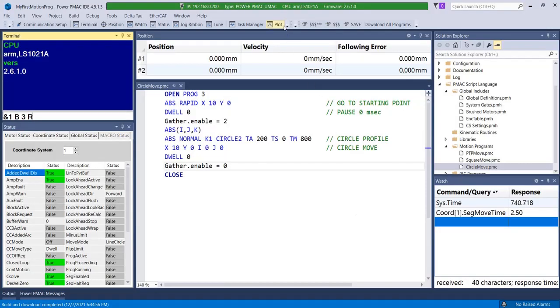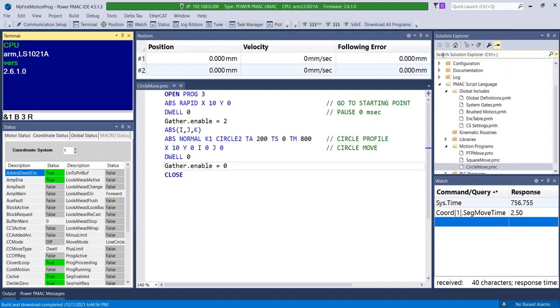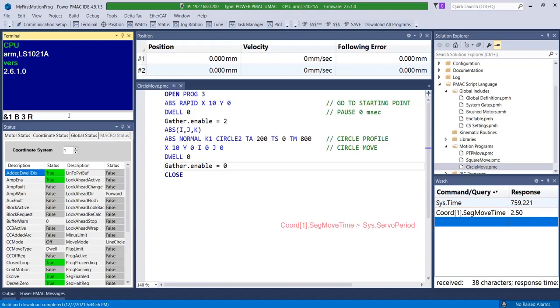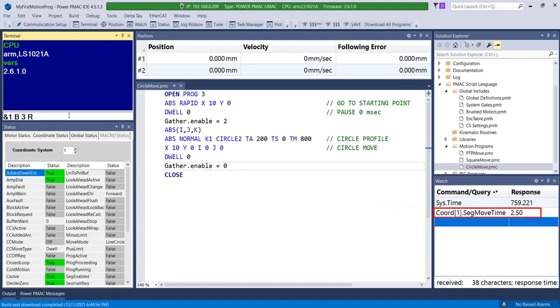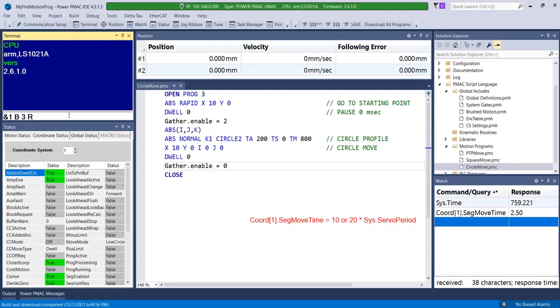This example contains a circle program. Setup the plot tool to view the output of the axes moves. Before a circle can be drawn, PMAC must be placed in segmentation mode by setting Coord1.SegMoveTime to a value greater than 0. It cannot be less than sys.servoperiod. Segmovetime specifies in milliseconds how often a new arc segment is computed, effectively controlling the resolution of a circle. The shorter the time, the better the resolution the circle will be. However, finer resolution comes at a tradeoff for a higher computational time for systems that have load constraints. Typical values for segmovetime are 10-20 times the servo period.